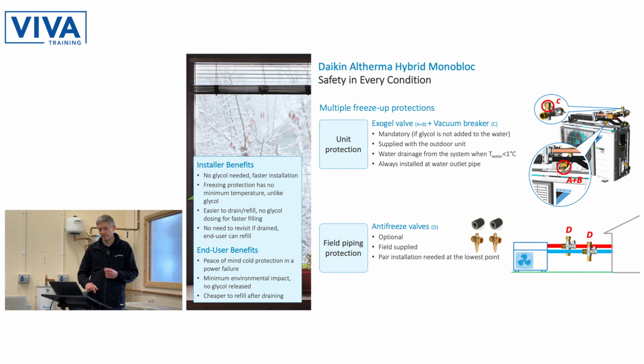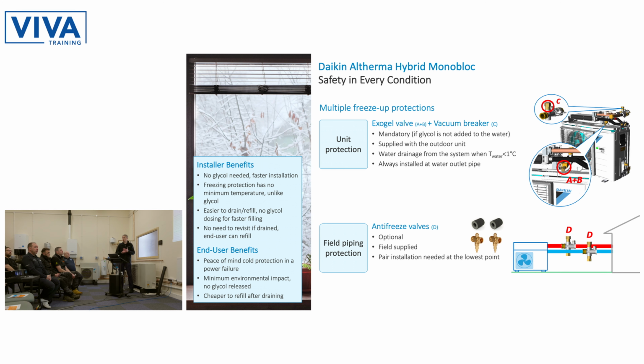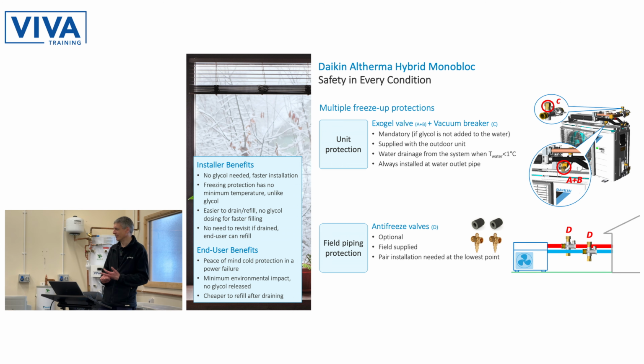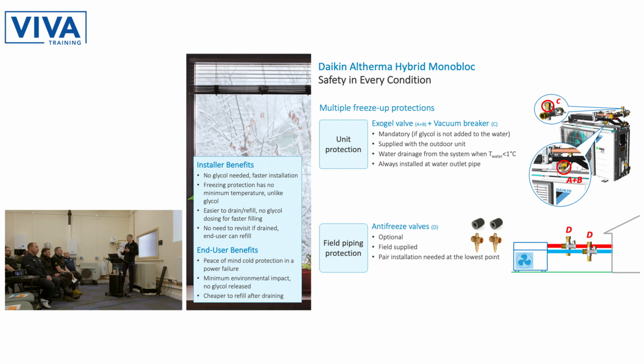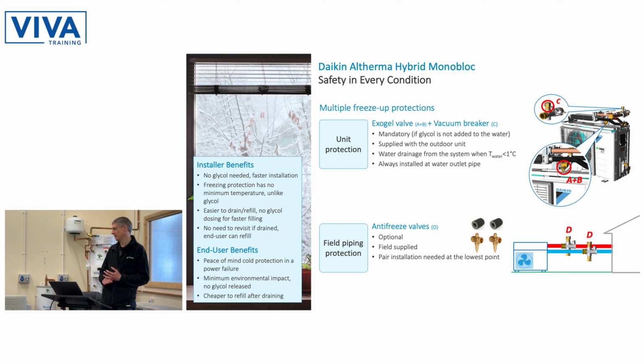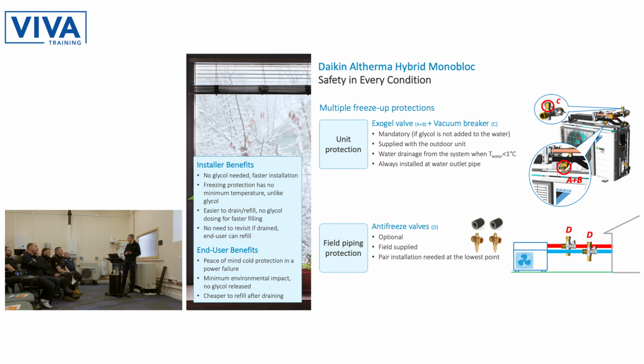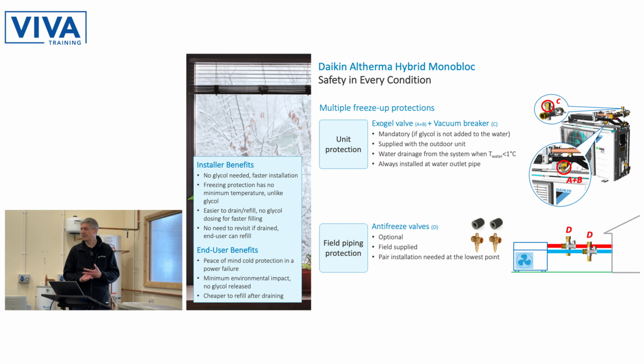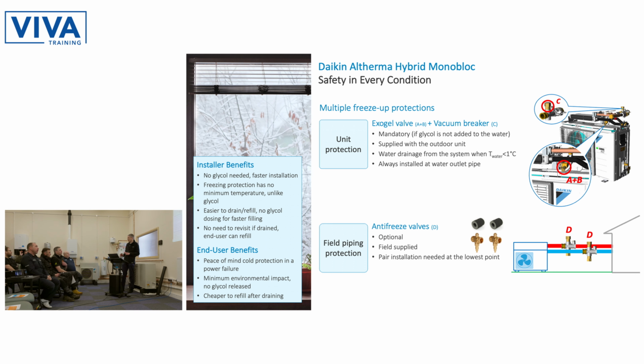Protection for the pipework, you could use glycol. Obviously that gives you protection, but it only offers you protection down to whatever level you've dosed it to. And it's a bit of a pain in terms of getting it dosed right. It takes longer, and glycol affects the efficiency. Absolutely that. So you can reduce the efficiency of the system depending on the dosage, 10, 20, 25%. So you could lose quite a bit of efficiency and even heat output from the system with glycol. So we're not saying absolutely don't use glycol, but our preference is not to use glycol.